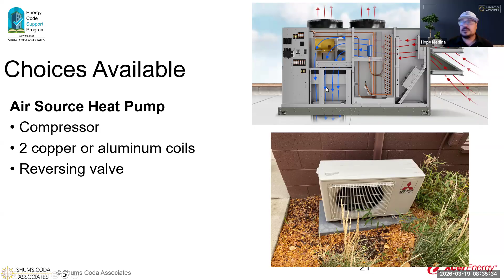Well, here is a really good breakdown. The outside coil is going to remove heat from air and evaporate into a gas. That's where the refrigerant is going to do that latent phase state change. That's that first step. The indoor coil is going to release the heat back from the refrigerant as it condenses back into a liquid. So again, we're taking advantage of that latency principle. And then the reversing valve is going to swap it from heating to cooling or cooling to heating. It's also going to assist with the defrosting process when the outside coil is in winter.